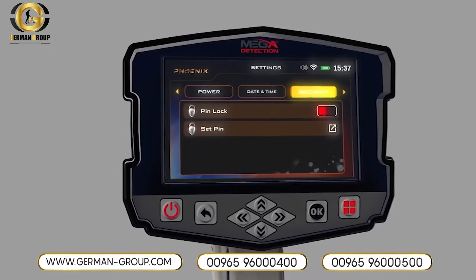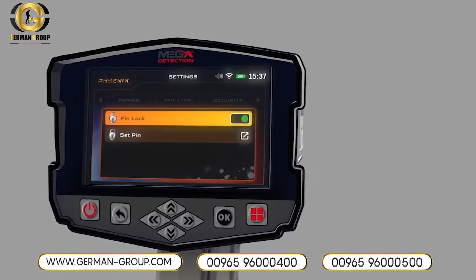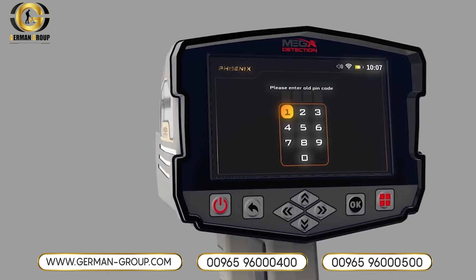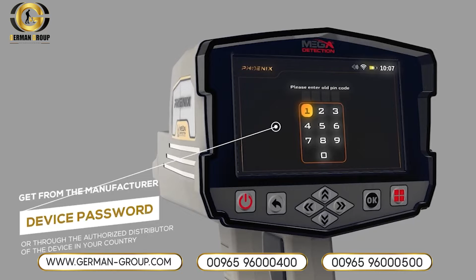Security settings. To activate the device's security settings, you must click on the Security Lock option within the Security settings. After activating the previous option, the Security Lock code can be set by the Set Security Code option. When operating the device for the first time, the device will ask you to enter the security code, device password, which you'll get from the manufacturer or through the authorized distributor of your device in your country. The security lock option can be locked in the device so that the device does not require the entry of the code after each operation.